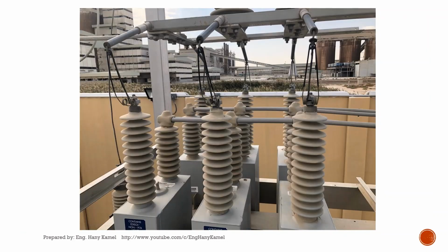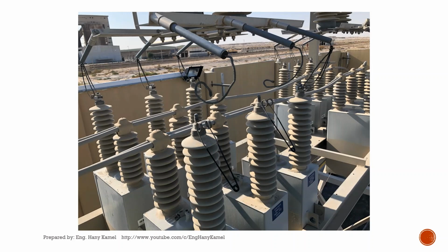In our example, each phase will have 6 capacitor units divided into 2 sections. Each section will have 3 capacitor units with 1 neutral. So we have 2 neutral points, as we can see in the photo. In this photo, we can see the neutral cable connecting the other 2 phases and going to the CT, as we can see in the next photo.